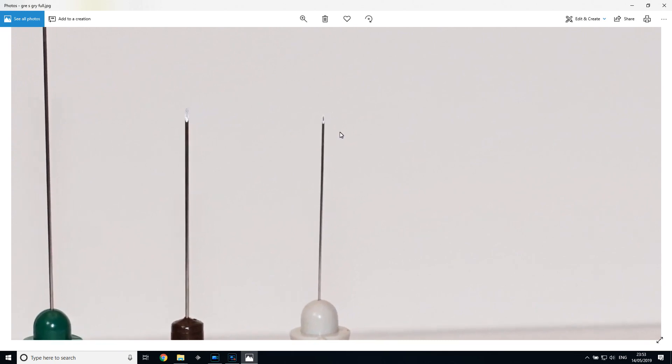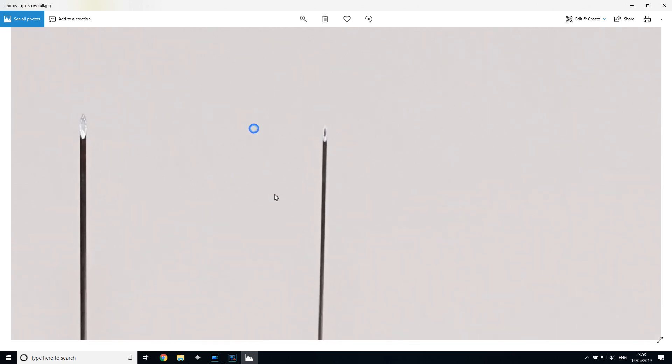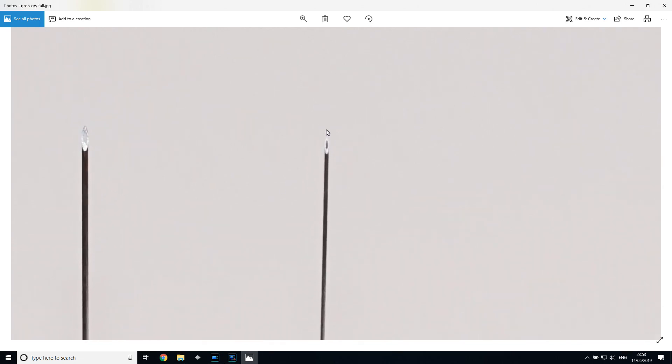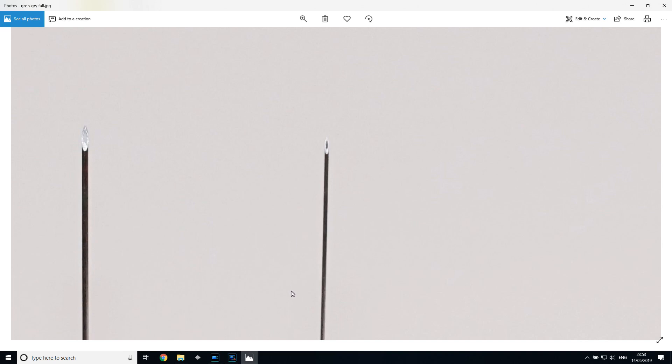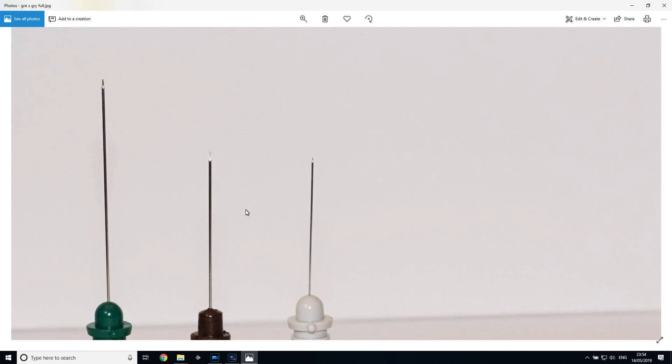Let's now contrast that to the 30 gauge facial needle from Ambu. And we can see first of all that the shaft is definitely narrower, so that's 0.3mm for these 30 gauge needles. And also the tip, the actual bevel itself, although of a similar shape to the single fiber EMG needle, actually is approximately half the size. And so therefore it's not surprising in our tests from the other day that it was much easier to pass through the Ambu needle as a comparison to the true single fiber EMG one.